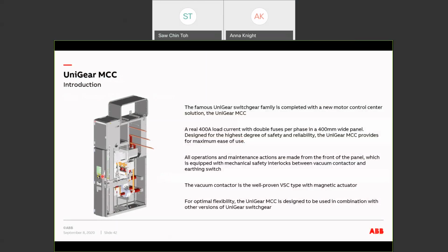Other than the standard UniGear ZS1 with withdrawable VSC contactor, we also have the UniGear MCC. This panel is only 400 millimeters wide. It has slim contactors, with a withdrawable VSC contactor sitting in the middle here. The 400 amps load current is possible by using a parallel, double fuse. This is ideal for a switchboard with many motor starters, for example in oil and gas, mining, process plants, or water utilities. This panel provides many benefits of UniGear panels in a very compact 400 millimeter wide dimension.